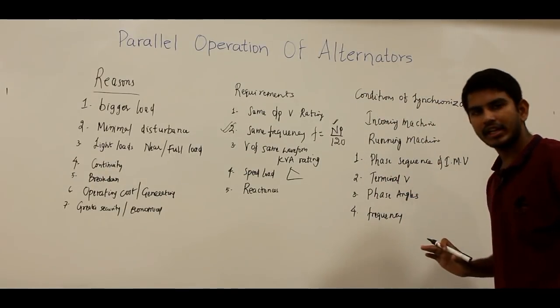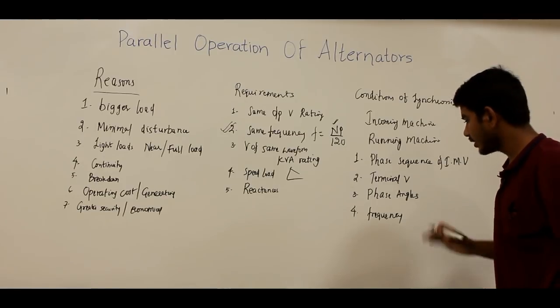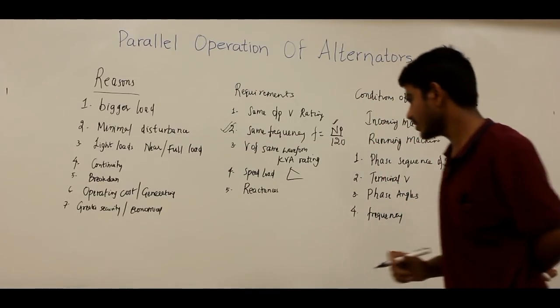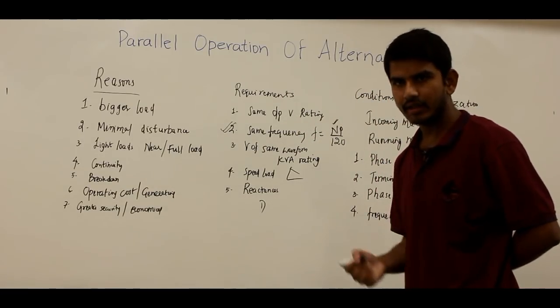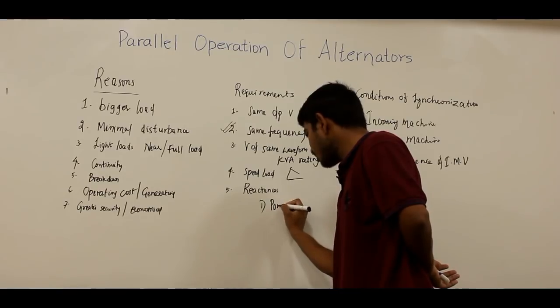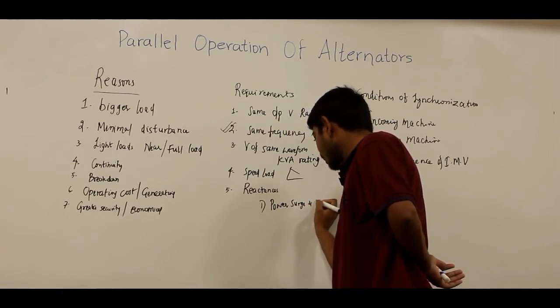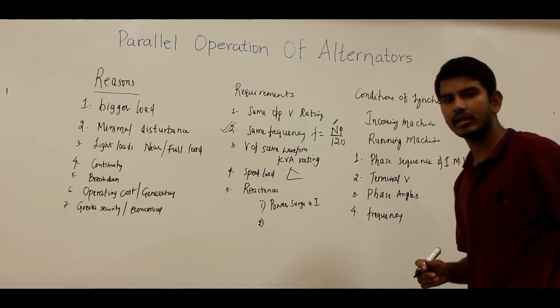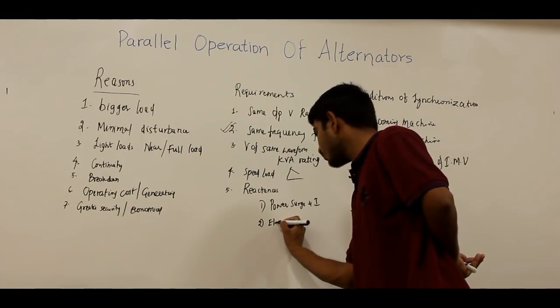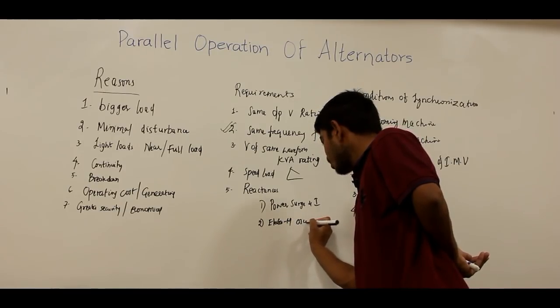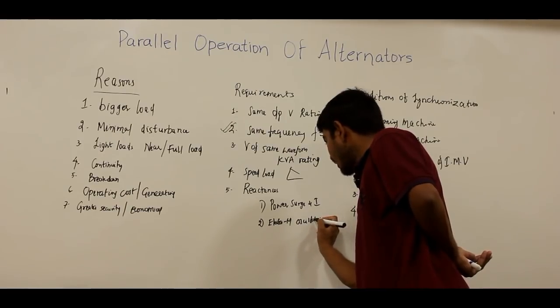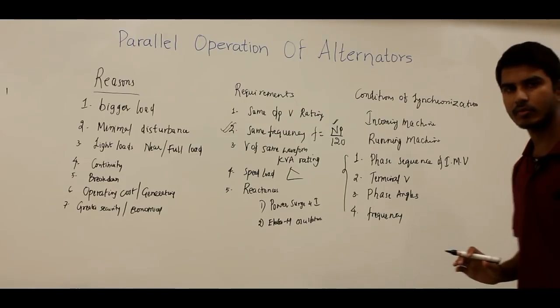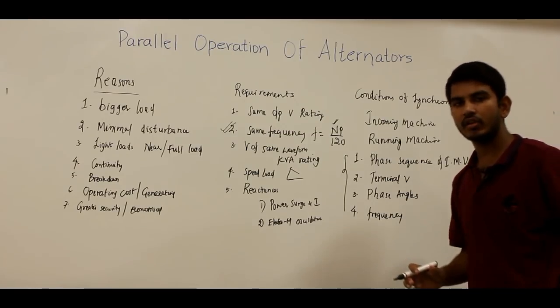If these four conditions are deviated or not satisfied, there will be two adverse effects. First, there will be high surges in power and current. Second, this results in the formation of electromechanical oscillation of the rotor, which may damage the equipment. Before synchronizing two alternators, we must check that all four conditions are satisfied, and then only the synchronizing switch is closed.